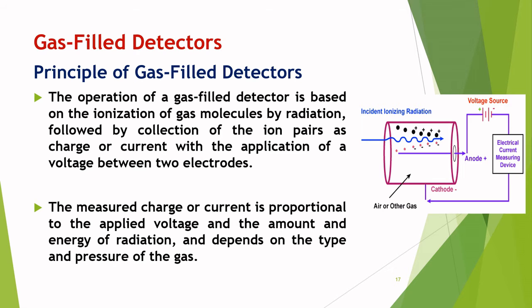Gas-filled detectors. Principles of gas-filled detectors. The operation of a gas-filled detector is based upon the ionization of gas molecules by radiation, followed by the collection of the ion pairs as charge or current with the application of a voltage between two electrodes. The measured charge or current is proportional to the applied voltage, and the amount and energy of radiation, and depends on the type and pressure of the gas.